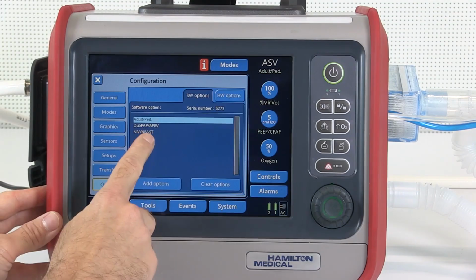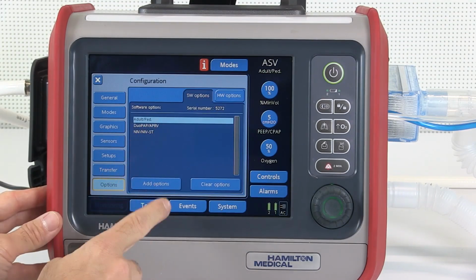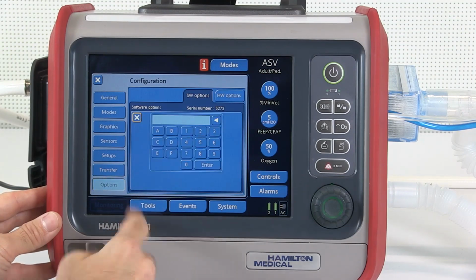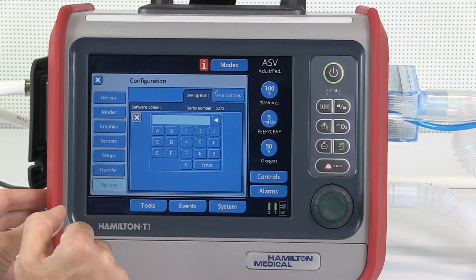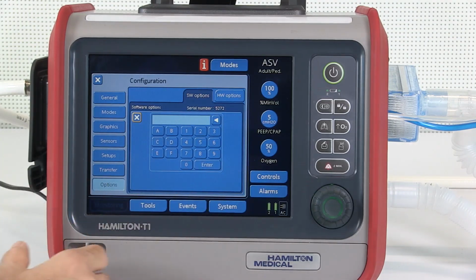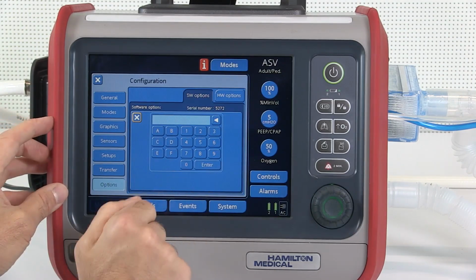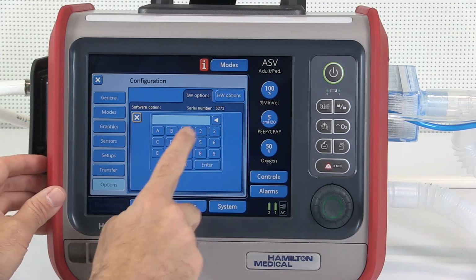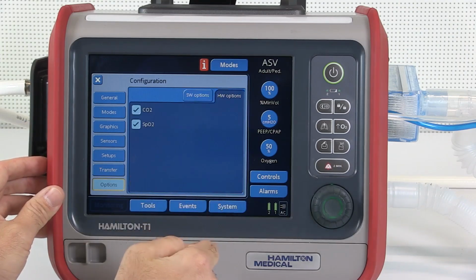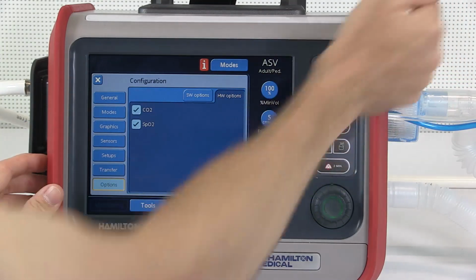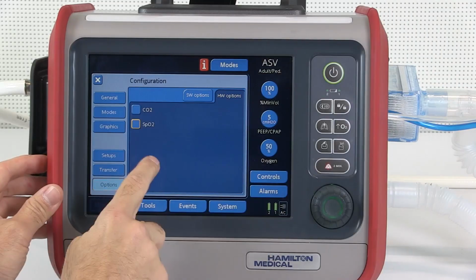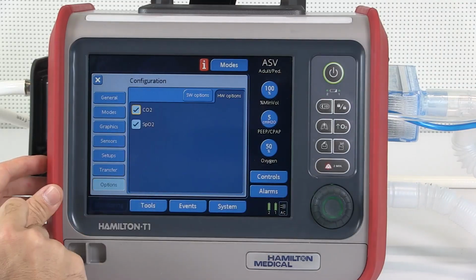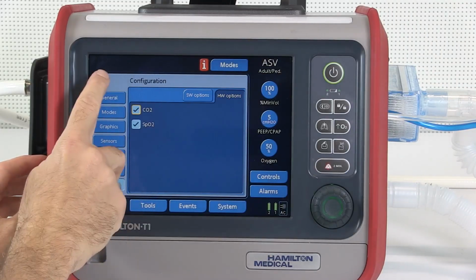Touch Options to review the installed options. If you need to add options, touch Add Options and type the activation code exactly as provided in the field. Then touch Enter. Please note that the activation codes are only valid for a specific ventilator unit depending on its serial number. Touch Hardware Options to activate or deactivate hardware options. Since we have a CO2 and an SpO2 option board installed in this ventilator unit, we can activate both options.